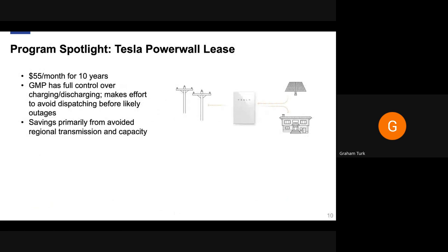The first program is one that's been running for about five years: a Powerwall lease. Customers lease two Tesla Powerwalls — 28 kWh of storage, roughly two to three days of backup if a home is relatively conservative during an outage. Two unique things about it: GMP actually owns the batteries. Customers receive the benefit of backup power, and GMP gets the benefit of a distributed fleet of batteries they can dispatch for avoiding transmission and capacity expenses. We'd have an installer go, install the battery, connect to it, and Tesla then managed these resources using their own forecast with full control over charging and discharging.